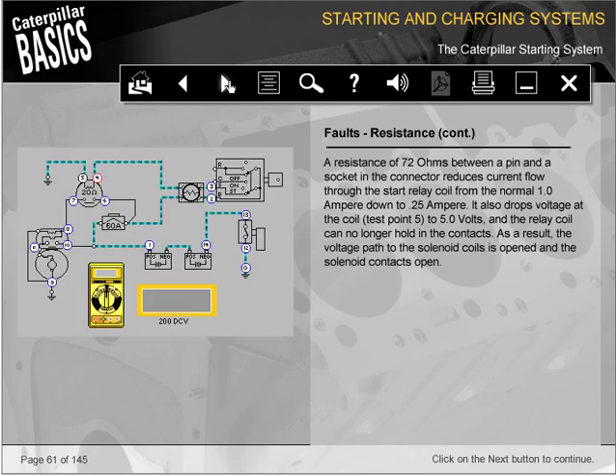A resistance of 72 ohms between a pin and a socket in the connector reduces current flow through the start relay coil from the normal 1.0 ampere down to 0.25 ampere. It also drops voltage at the coil, test point 5, to 5.0 volts, and the relay coil can no longer hold in the contacts. As a result, the voltage path to the solenoid coils is opened, and the solenoid contacts open.